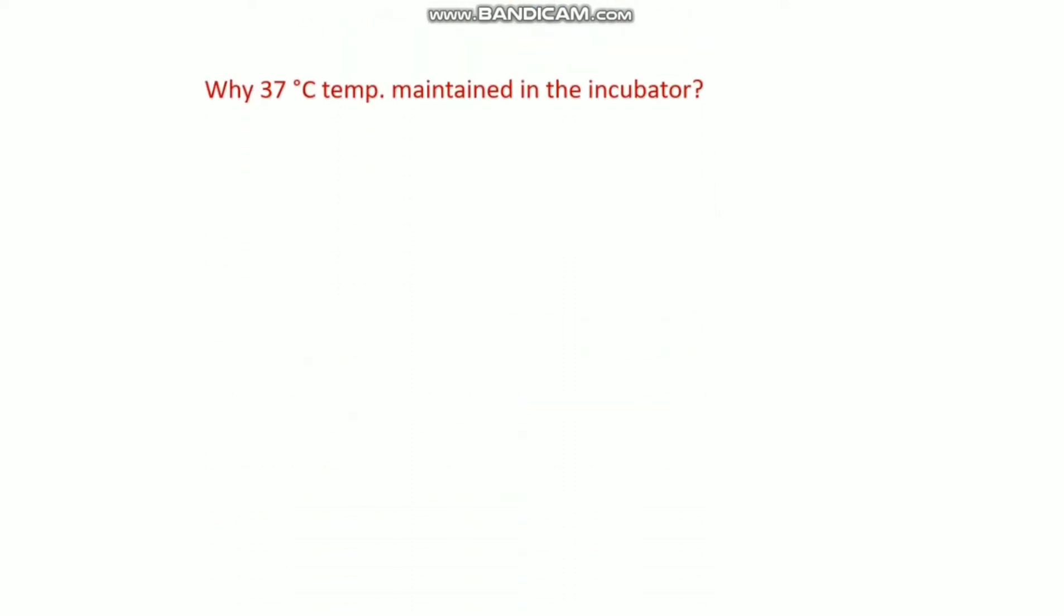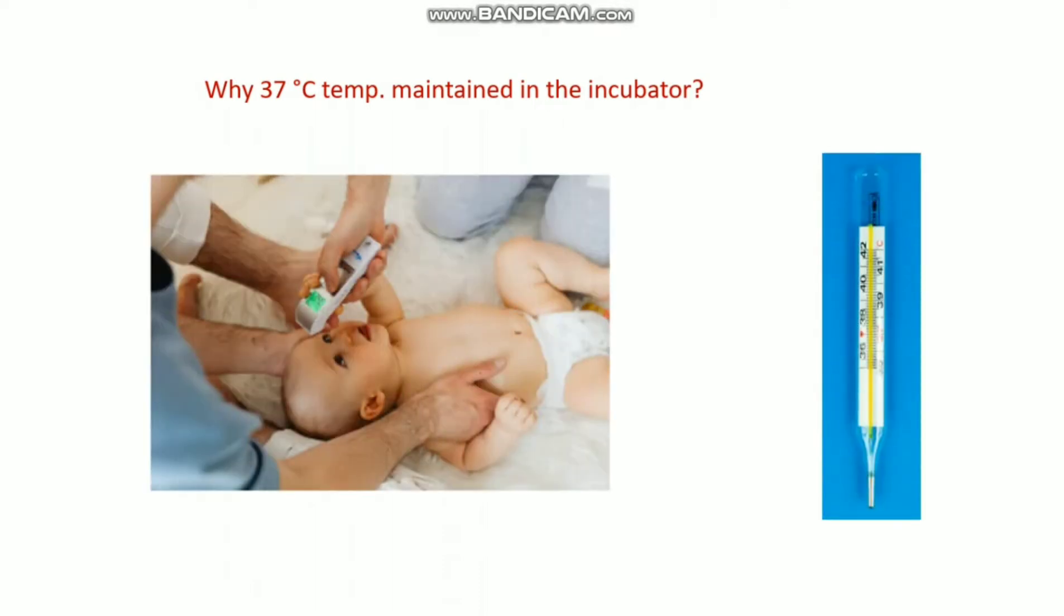First let's talk about why 37 degree temperature is maintained in the incubator. This is very simple. All of the mammalian cells and most living organism cells require 37 degree temperature to grow. This is why this temperature is maintained in the incubator to grow the cells properly.